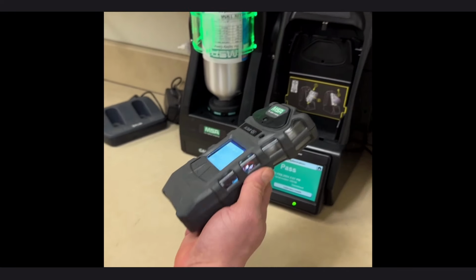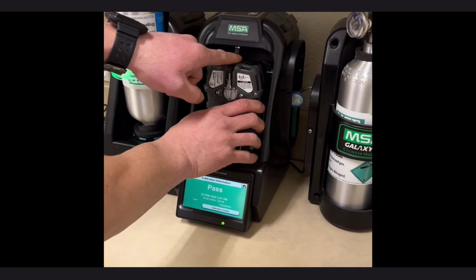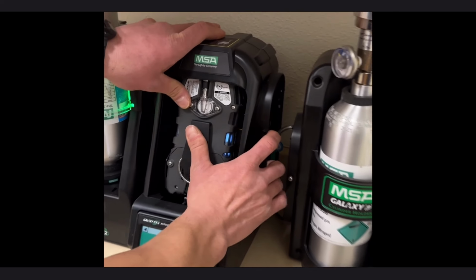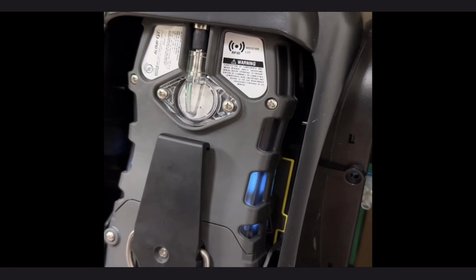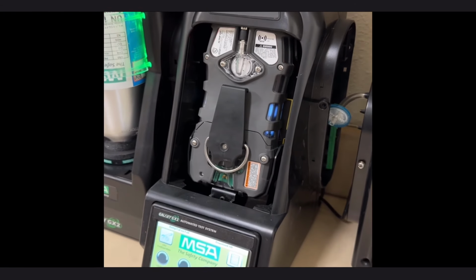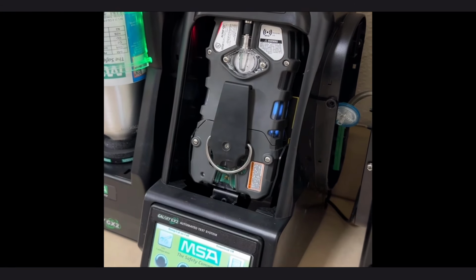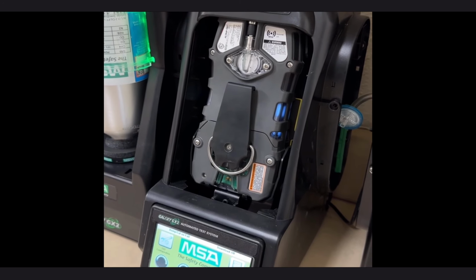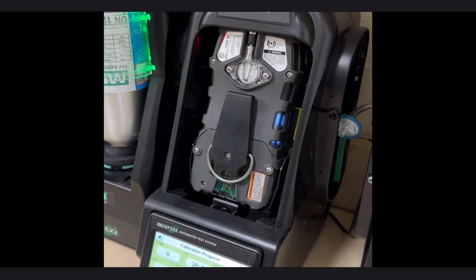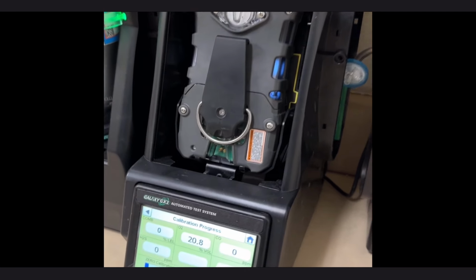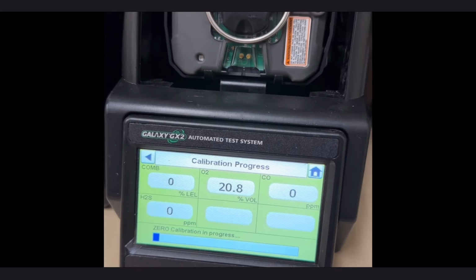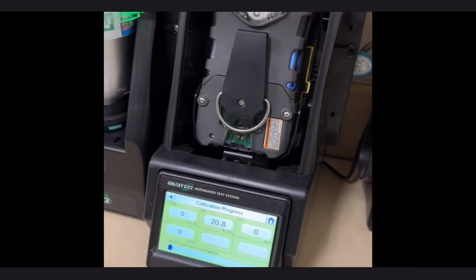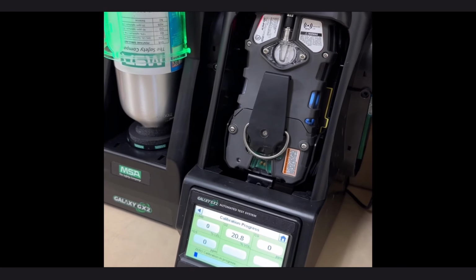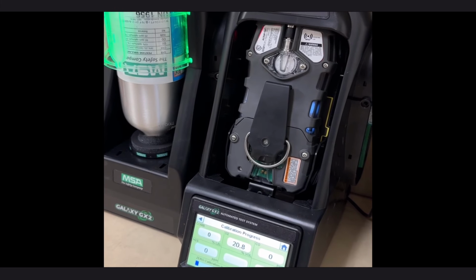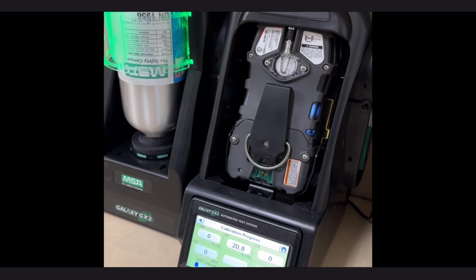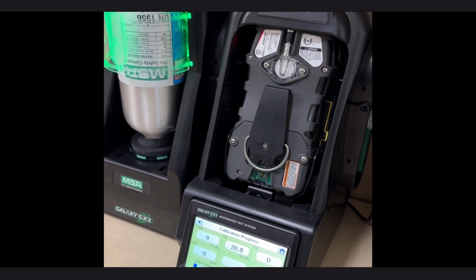The big thing on these is, you flip it away from you, it's got this little port. You just need to make sure that the pump pushes up into that port and locks. And then the screen will take a minute, and then it'll start auto calibrating, and at the end you'll see that pass green banner, and you'll see it in progress right now. Just like our old monitors, it'll take a little bit. At the end of it, it'll give you the option to fresh air setup again, which means once again you're going out in a clean atmosphere, just running air over the sensors and diluting it with whatever's residual on them, so you don't have those 1, 2 readings that are residual.